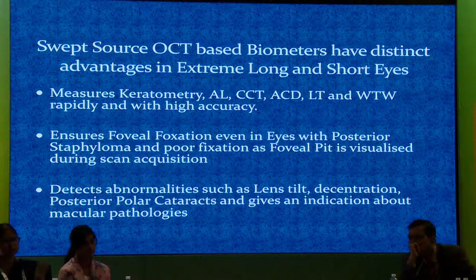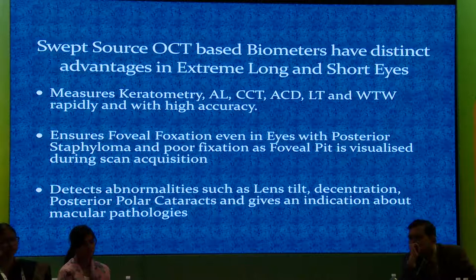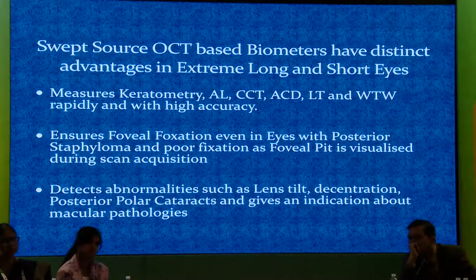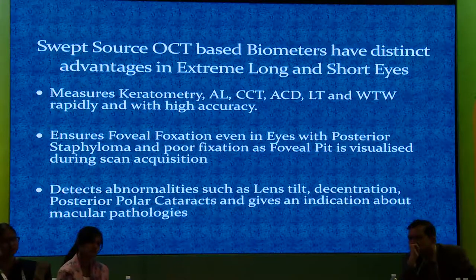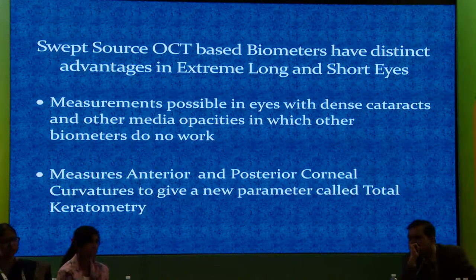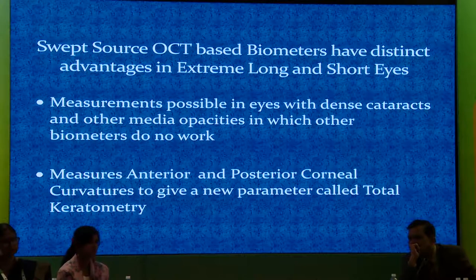These devices measure keratometry, axial length, corneal thickness, ACD, lens thickness, and white-to-white — so you have more variables. They ensure foveal fixation. Importantly, if you have a posterior staphyloma with poor fixation or a foveal pit, it is visualized during the scan. If you have a scar at the macula, it is also visualized. Measurement is possible in eyes with denser cataract, and it measures anterior and posterior curvature of the cornea simultaneously, giving you total keratometry.